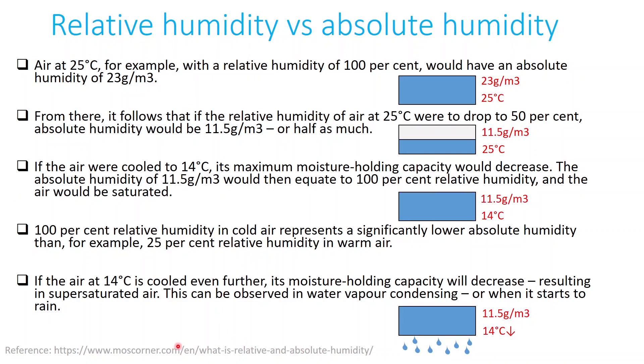Here are some examples. At 25 degrees with 100% relative humidity, we will have an absolute humidity of 23 grams per cubic meter. If we keep the temperature constant at 25 degrees and reduce the relative humidity to 50%, this means we have an absolute humidity of 11.5 grams per cubic meter, basically half. With this absolute humidity of 11.5 grams per cubic meter, if we decrease the temperature from 25 degrees to 14 degrees, we will end up having 100% relative humidity at 14 degrees Celsius. This is because the maximum moisture holding capacity of air decreases with a decrease of temperature.